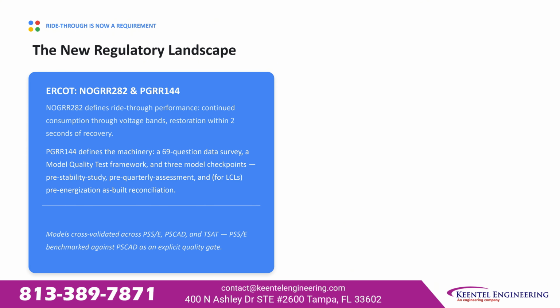NOGRR 282 defines ride-through performance itself, continued consumption through defined voltage bands with restoration within 2 seconds of recovery. PGRR 144 defines the process, a 69-question data survey, a model quality test framework, and 3 model checkpoints: pre-stability study, pre-quarterly assessment, and for large controllable loads, pre-energization as built reconciliation. Models get cross-validated across PSS/E, PSCAD, and TSAT, with PSS/E benchmarked against PSCAD as an explicit quality gate.